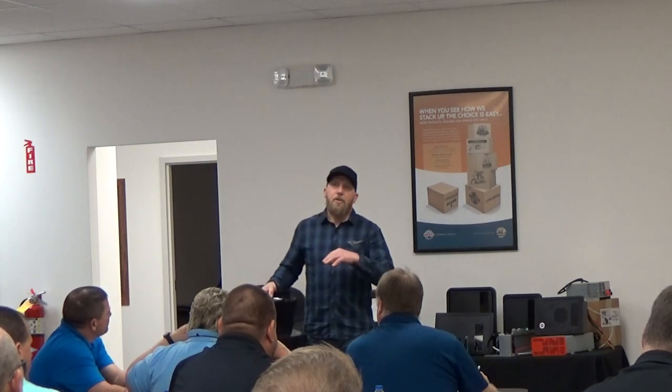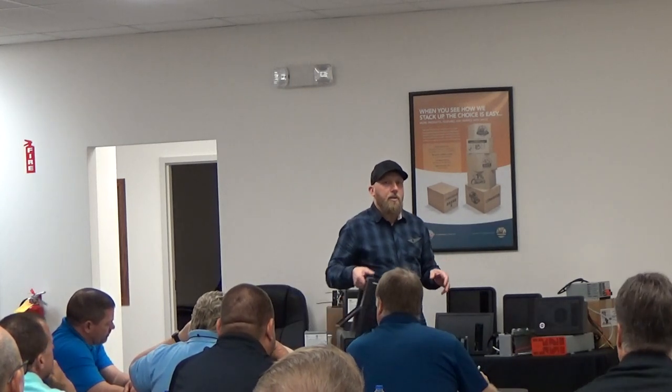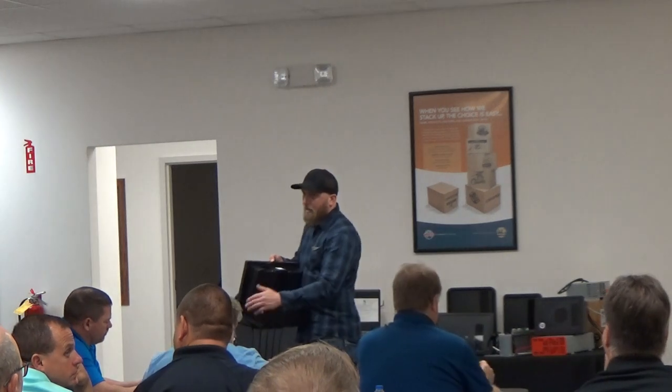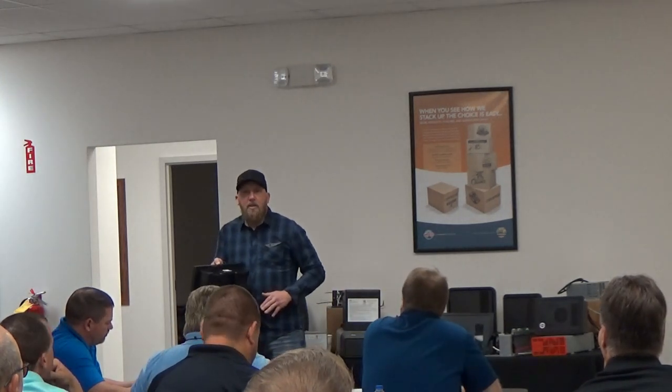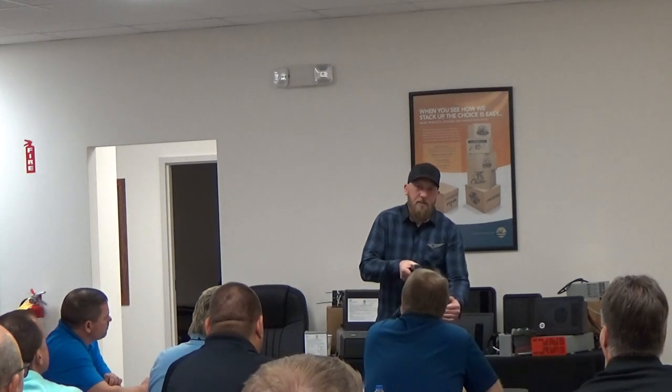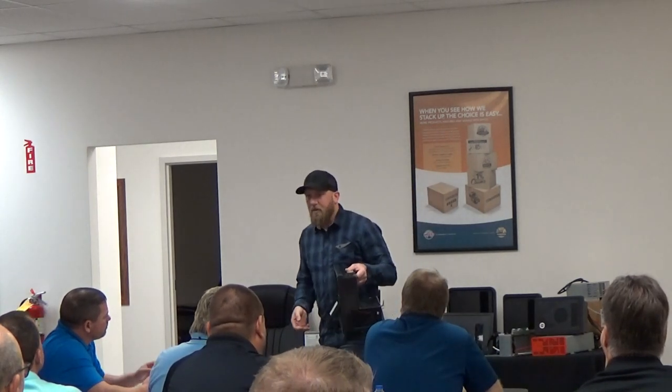That's what our auditors do when they go out to these factories. They see where they're installing these, making sure they're not in a zero clearance space where it could be overheating or anything like that. We've had them where heat ducts are laid across these, or just things that don't make sense, because it does suck in air through the back and blow it out the front.